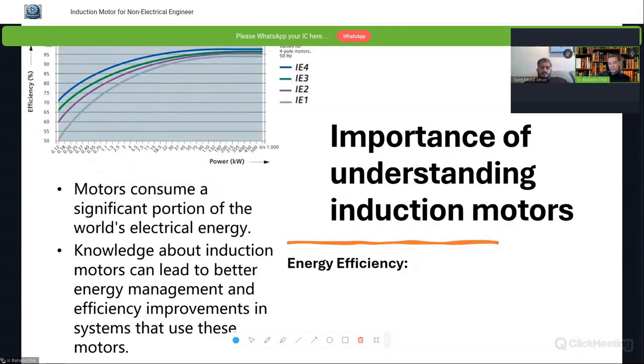And also, since most of the process equipment are motors, we need to understand the working principle of induction motors so that we can be very efficient in terms of energy requirement. For motors, we have four efficiency classes by IEC. We have IE1, that is the standard efficiency. We have IE2 for high efficiency motors, IE3 for premium efficiency, and IE4 for super premium efficiency.